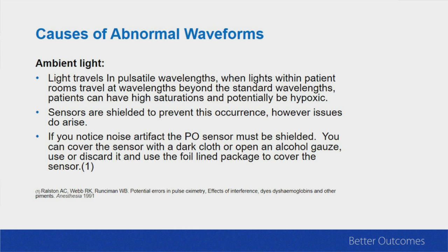And generally, it's going to be in the 50 to 60 hertz is what it's going to travel at. But other lights in the room, if they're traveling at wavelengths outside of that 50 or 60, are going to cause problems with our pulse oximeter, and we're going to end up having high saturations when actually the patient could be hypoxic. Now, the manufacturers, obviously, a long time ago figured out this issue and started shielding sensors to prevent this. So I'll show you an example of this a little bit later.